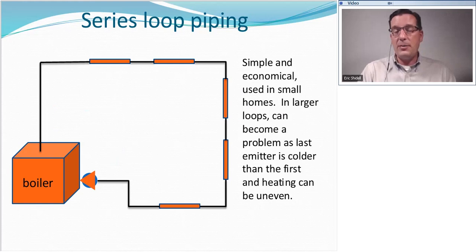Series loop piping is very simple. We have one pipe leaving the boiler as supply, and it enters the first emitter, leaves the first emitter, and goes right into the second emitter. Very simple, very economical, and was frequently used in smaller homes. And when I say small, I generally mean under 1,000, 1,100 square feet.